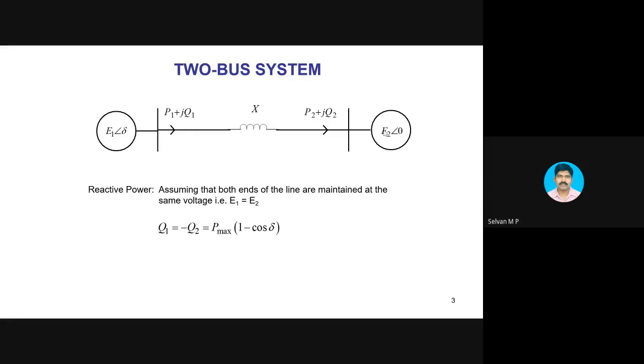Right. So our interest is on reactive power in the system. So I assume voltage at both the ends are equal. Somehow I am maintaining that. If I maintain, I have to do something, right? Without that I cannot maintain, definitely, because the sending end voltage is E1. When the current flows through X, definitely there will be a drop. Then I have to maintain E2 at the same value of E1. How can I maintain that? Definitely there is a drop.